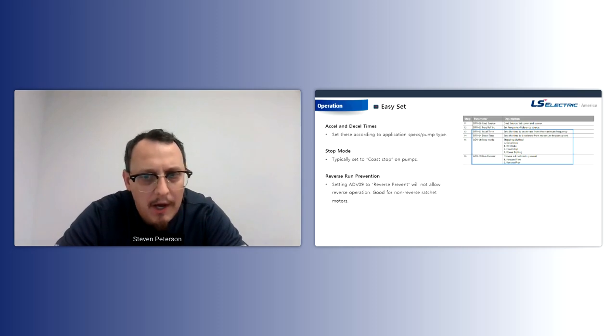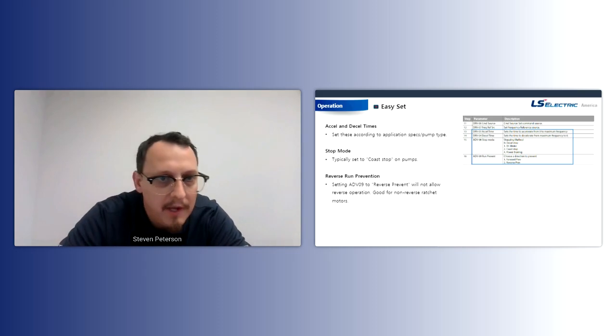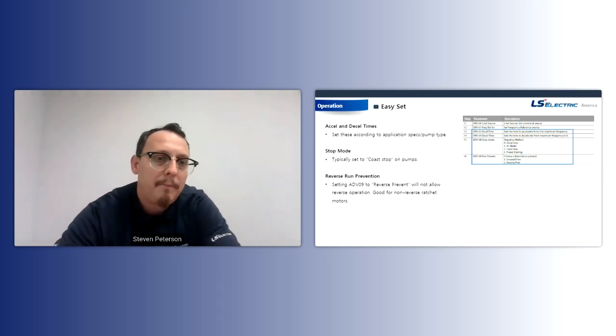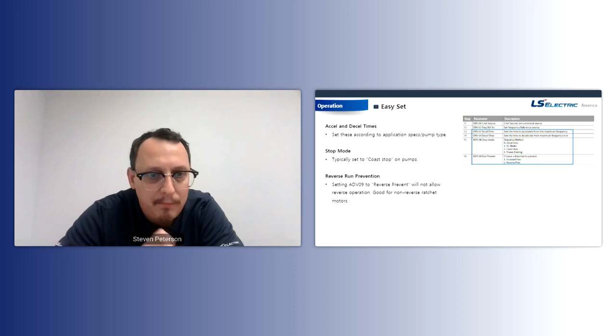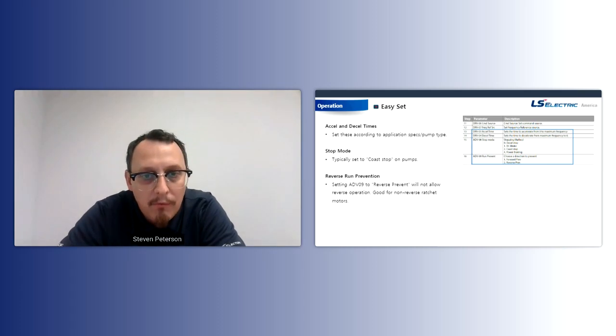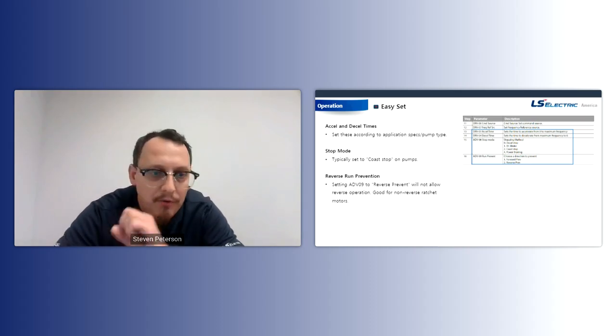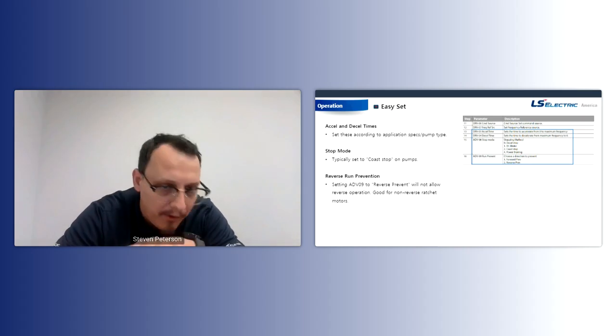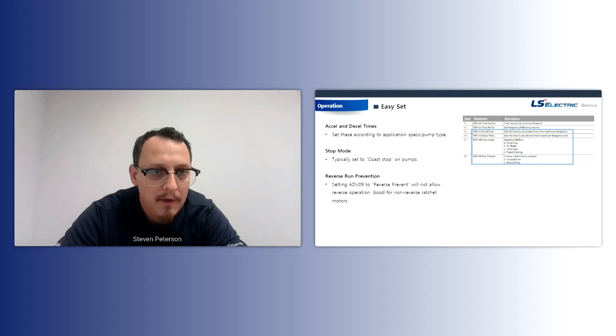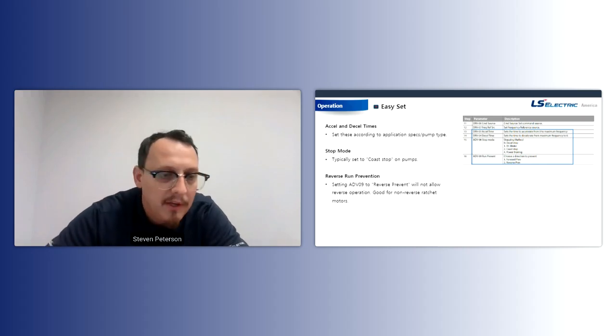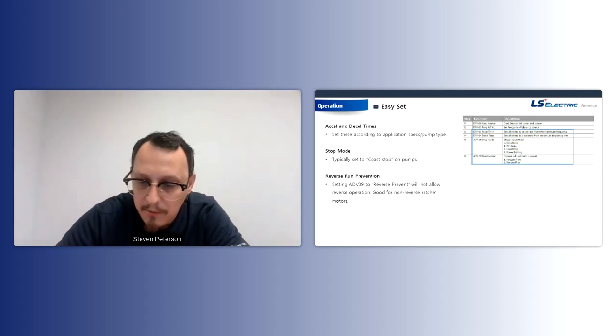Okay. The last thing we'll mention here before we jump into the next group of setting parameters on basic setup is reverse run prevention. This is especially good if you have a non-reverse ratchet type motor where you're not allowed to run in reverse. Mechanically it's locked out. We have a reverse run prevent. So if you set this to reverse run prevent, even if we unknowingly try to run the pump in reverse, it's locked out via parameter. So it's impossible to run in reverse unless somebody takes the extra step to go into that parameter and undo whatever you did when you started it up. So that's a nice protection parameter that's built into this VFD, and it's in the easy start menu.